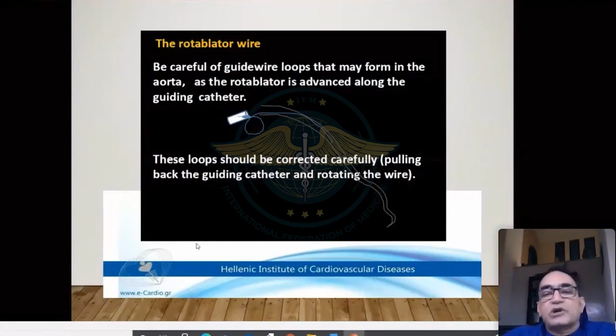Now you can see here, this is the wire clip torquer. This is a torquer on the rota wire, which it enters from the side. That is the speciality of this one. Although it is called the torquer, we rarely use it for torquing. We always use a microcatheter to put the wire inside. The idea of this wire clip torquer is to hold the wire powerfully and carefully so that it does not rotate when the rota burring takes place. The rota is a very high speed burr. It goes up to as high as 1.5 lakhs or 1.6 lakhs per minute, and therefore it can rotate the wire, and we don't want that to happen.